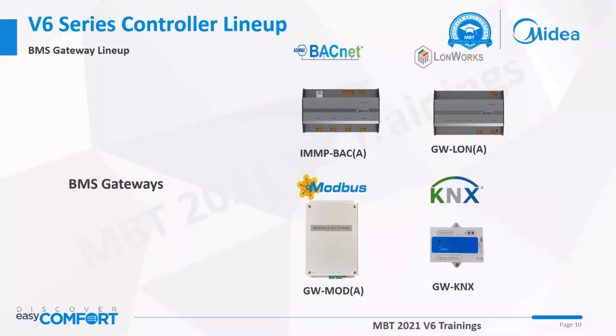The next part is for the BMS gateways. For the BMS gateways, again, we are compatible with all major BMS languages, that is BACnet, LonWorks, Modbus, and KNX. For these gateways, just the capacities are different. I can tell you what the capacities are. So you can see here there are 4 XY ports, XY 1, 2, 3, 4. Each port can connect 8 systems and 64 indoor units. So this one can connect 256 indoor units, connected to the outdoor unit side.